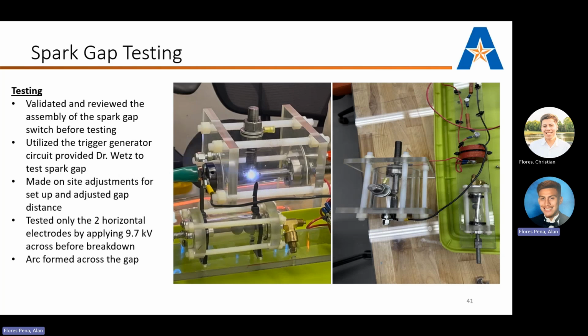For testing, given that we did not have our trigger generator circuit available at the moment, we utilized the trigger generator circuits that Dr. Wetz had previously developed. We made some on-site adjustments to set up the circuitry for our spark gap switch, and adjusted some of the gap distances, specifically since we wanted to test only the two horizontal electrodes. Once we applied 9.7 kilovolts across both electrodes, we were able to form the arc that we wanted for our spark gap switch. And for that purpose, we were able to see success between our two electrodes and our spark gap switch.